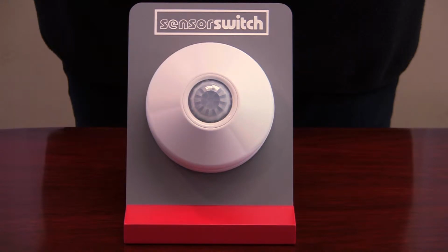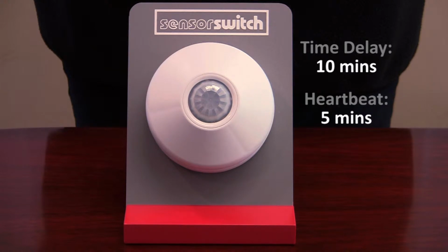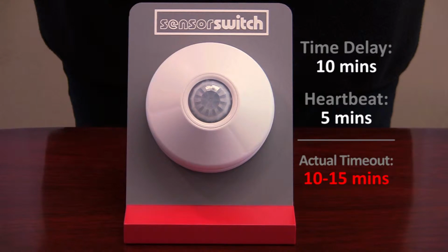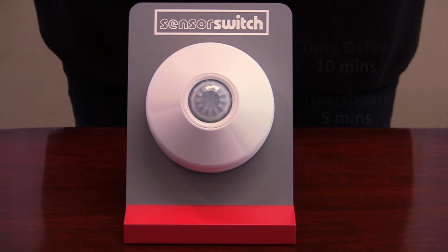Functionally, this means that if you have the receiving switch's time delay set to 10 minutes with a 5-minute sensor heartbeat, the actual time it will take for the sensor to turn the lights off after leaving a space is between 10 and 15 minutes, depending on how long after the last heartbeat transmission the space was vacated.